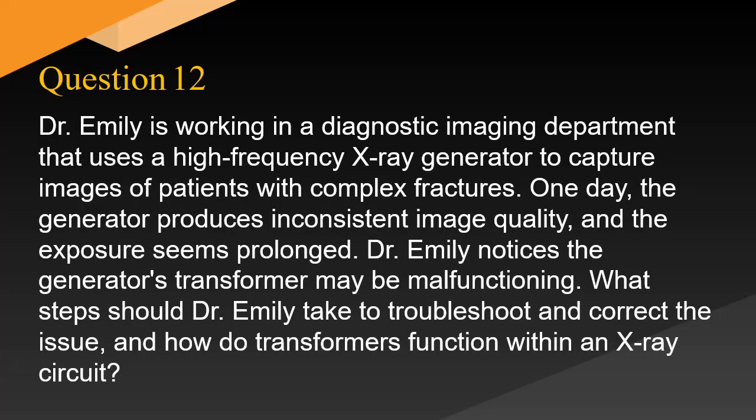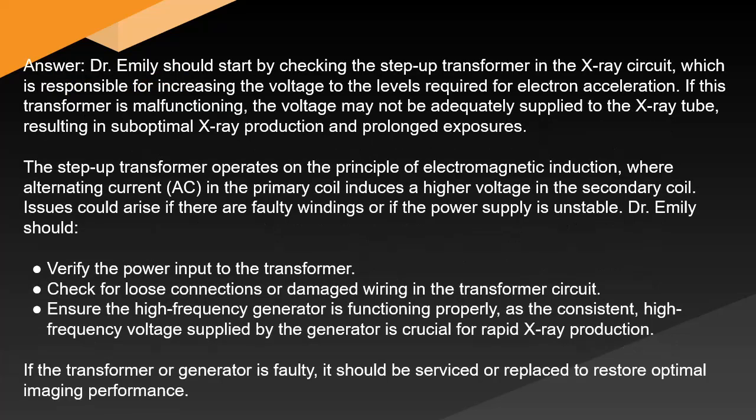Dr. Emily is working in a diagnostic imaging department that uses a high-frequency X-ray generator to capture images of patients with complex fractures. One day, the generator produces inconsistent image quality, and the exposure seems prolonged. Dr. Emily notices the generator's transformer may be malfunctioning. What steps should Dr. Emily take to troubleshoot and correct the issue, and how do transformers function within an X-ray circuit? Answer: Dr.